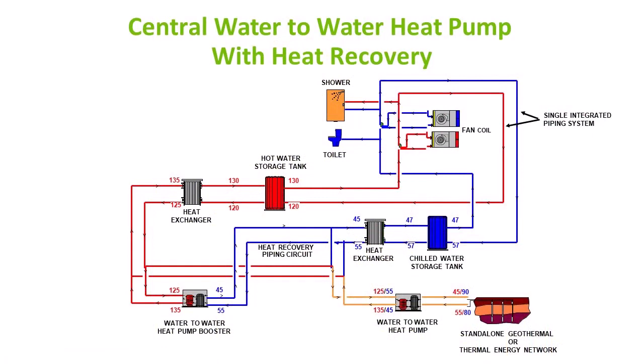Okay? All right, here's the same thing, but we're going to use a geothermal source in the lower right-hand corner. There we don't need the booster because we're going to get adequate temperatures out of that geothermal heat pump. The industry talks about low temperature heat, okay? Those heat pumps, the geothermal, they still have about 100 degree lift. So if you got 40 degree water, you only get 140.